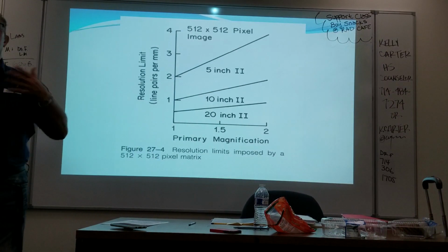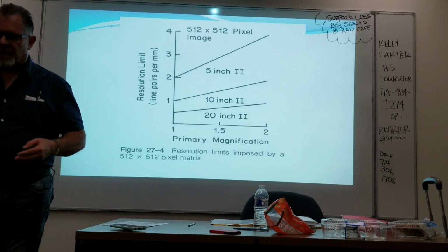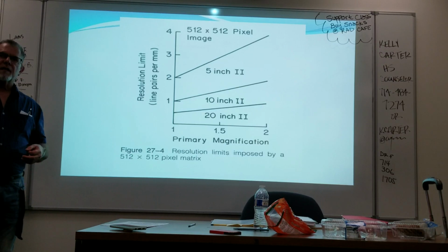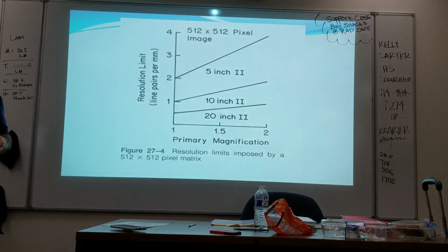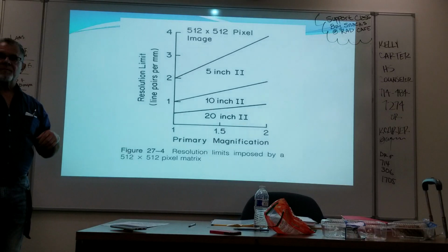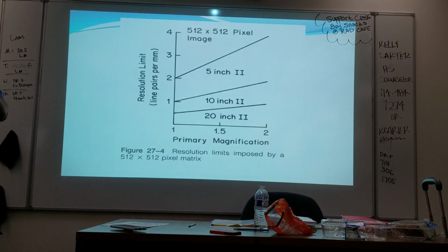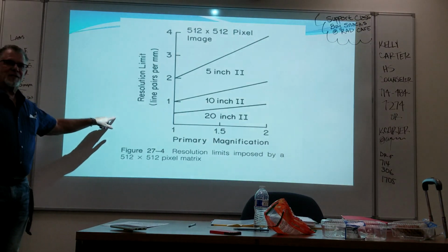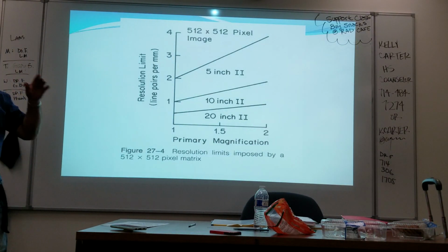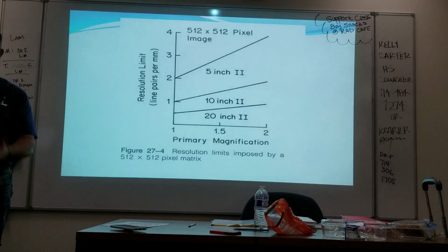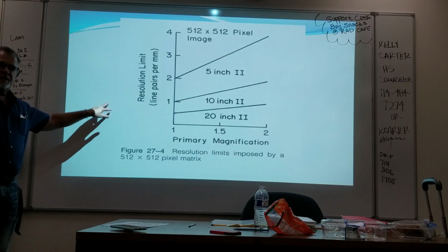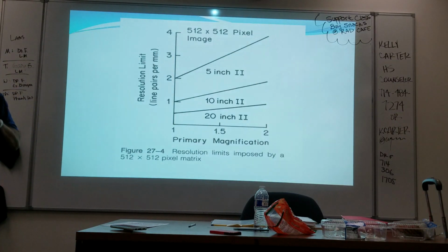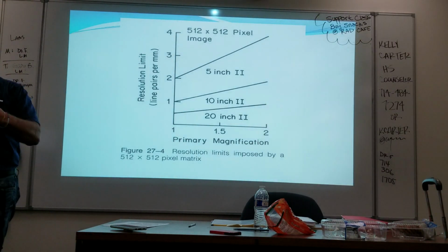What do you have to do? What does the system do? Increase technical factors. It increases your automatic brightness system, so it's pumping out more X-ray to keep that image the way it's supposed to. At some point, that's going to lead to what? A failure of your weekly fluorocheck test, because it's going to go outside the bounds because the gain has decreased so much, the equipment's pumping out a lot more exposure, you reach that 25% point, it's like, oops. So now you require recalibration by the engineer to bring it back into spec.